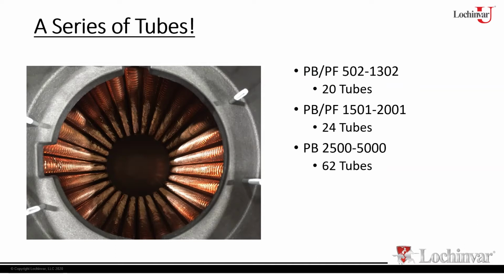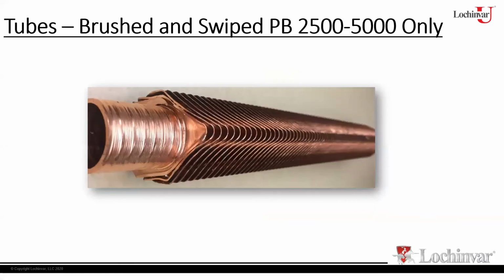So basically, we have 2 layers, an inner layer of tubes and then an outer layer of tubes. How we get those all to fit together is based on a brushing and swiping method. This would be the tube that you would see in the larger models. This is our standard copper tube. This is a 99.9% pure copper tube. We do have the option for copper nickel if someone wishes, but the standard tube would be pure copper. Again, the fins as it comes in, it would be a thin copper tube all the way to the end. This is a good picture that shows the de-finning process here. It shows where we've cut off about 1 inch of those copper fins from the front end as well as the back end to allow that to slide up into the header for the rolling process.